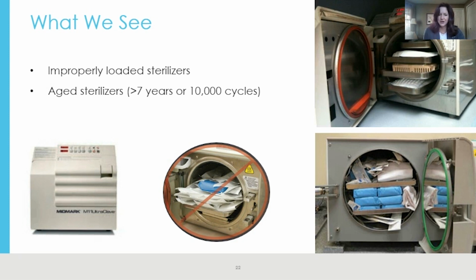The solution here addresses loading and sealing pouches correctly and placing them in the autoclave correctly. We recommend the use of pouch racks. Our sterilizers do come with a pouch rack, and you can also order cassette racks. By utilizing these racks and loading your instrumentation and pouches on edge, this keeps them from laying flat and burning. We've all had those bottom racks come out of the autoclave kind of burnt on the edges, so this alleviates that problem. Having the racks also allows you to put more pouches into your autoclave - it's more efficient, so you're not packing your autoclave full. You'll get many more instruments and pouches in using racks.